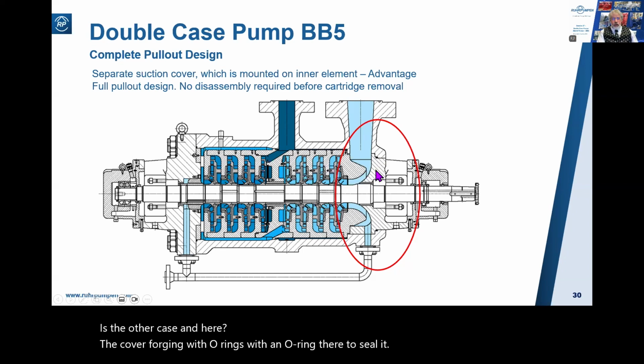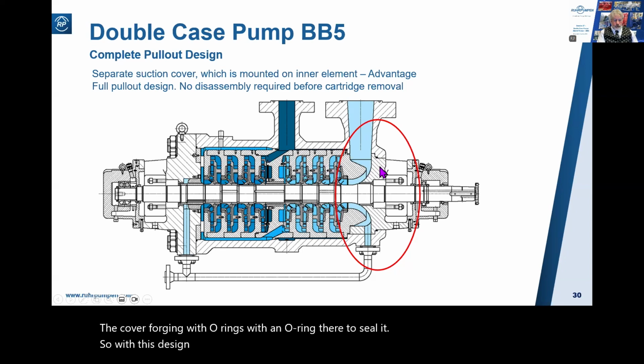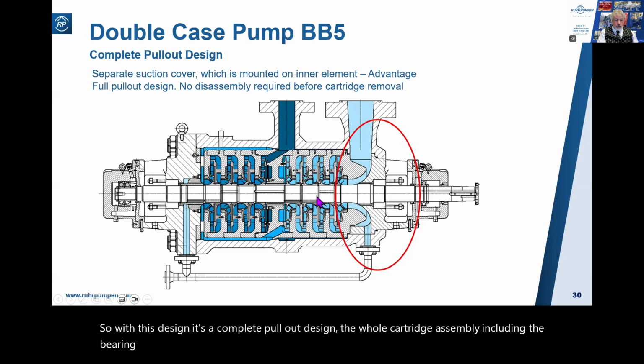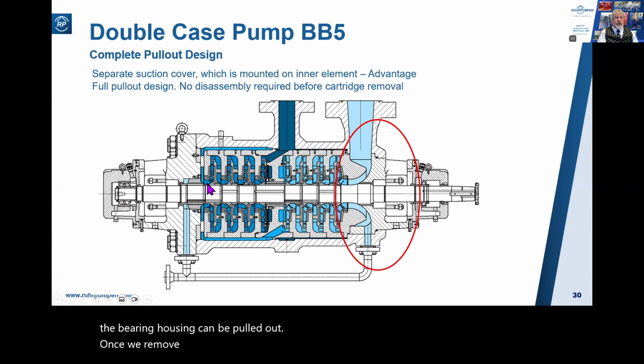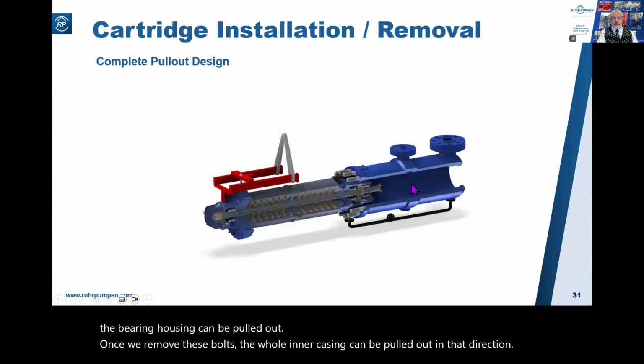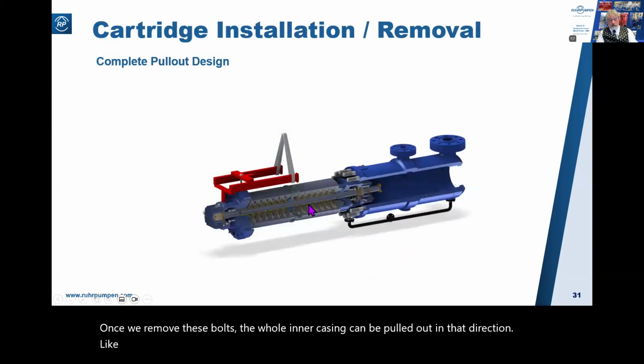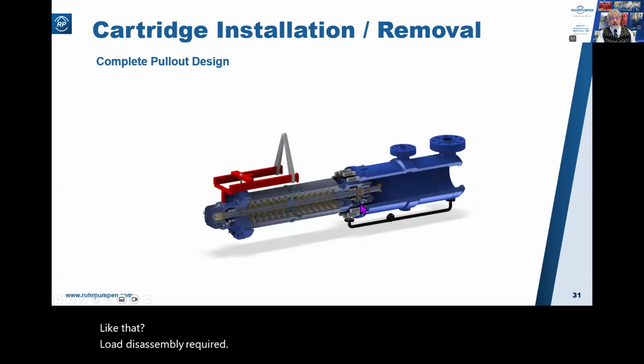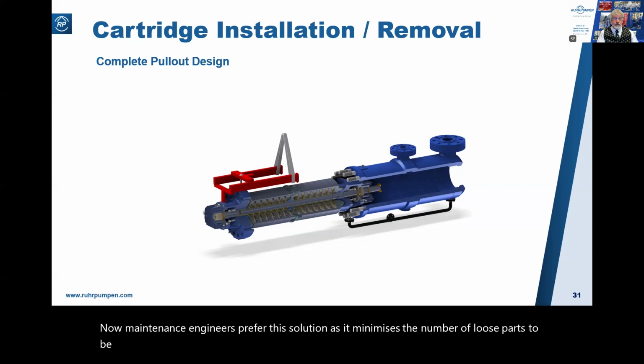So with this design, it's a complete pull-out design. The whole cartridge assembly, including the bearing housing, can be pulled out. Once we remove these bolts, the whole inner casing can be pulled out in that direction, like that. No disassembly required. Now, maintenance engineers prefer this solution as it minimizes the number of loose parts to be tracked and handled.